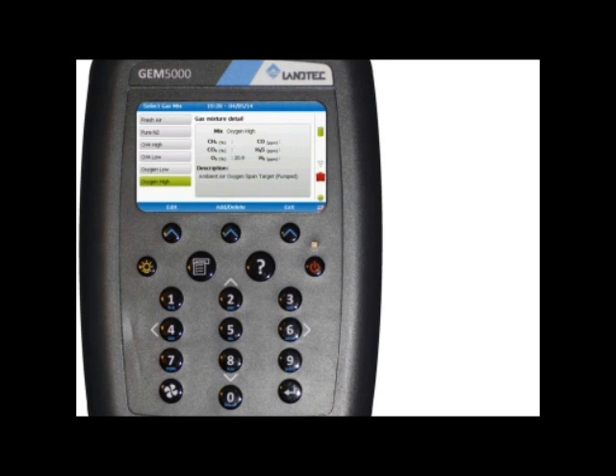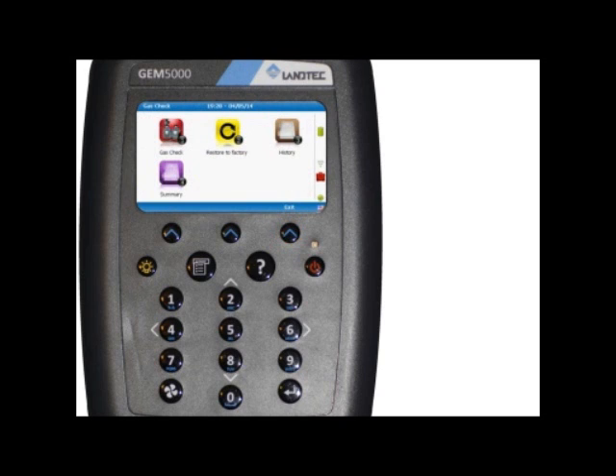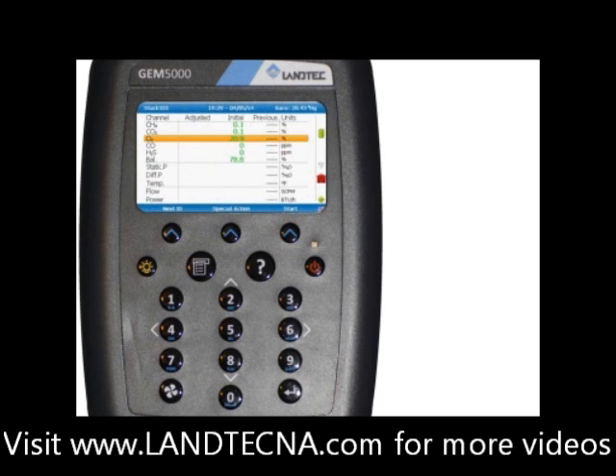Now you're back at the select gas mix. At this point, you have successfully calibrated your GEM5000, and now you can exit back to the main reading screen to start taking readings by pressing exit. From the gas check screen, press the right soft key again to exit. Once more to exit from the menu screen. Now you're back at the main reading screen, and now you should be able to start taking readings.